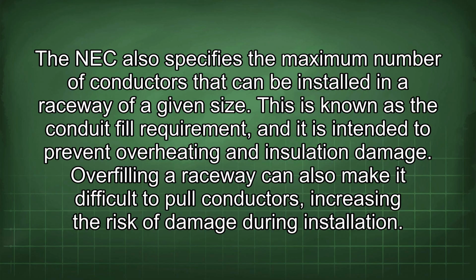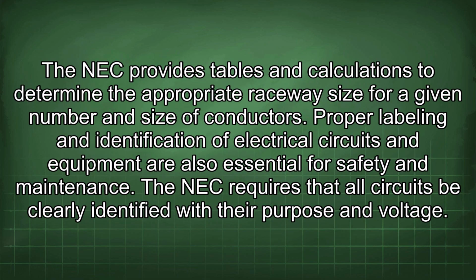The NEC also specifies the maximum number of conductors that can be installed in a raceway of a given size. This is known as the conduit fill requirement, and it is intended to prevent overheating and insulation damage. Overfilling a raceway can also make it difficult to pull conductors, increasing the risk of damage during installation. The NEC provides tables and calculations to determine the appropriate raceway size for a given number and size of conductors.